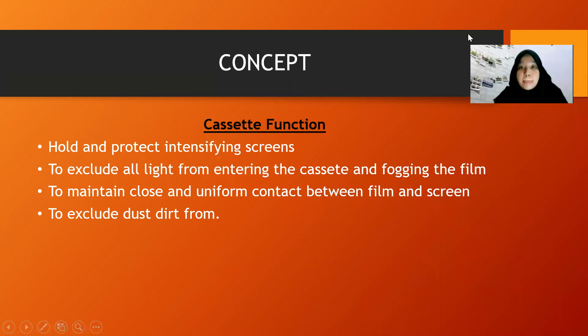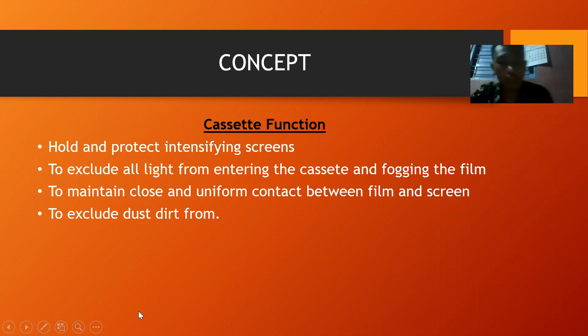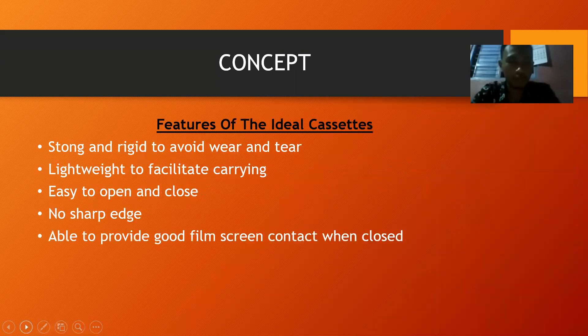The functions of the cassette are to hold and protect the intensifying screen, to exclude all light from entering the cassette, and to maintain close and uniform contact between film and screen. Features of the ideal cassette: long-lasting and durable to avoid wear and tear, lightweight to facilitate carrying, easy to open and close, no sharp edges, and able to provide good film-screen contact when closed.